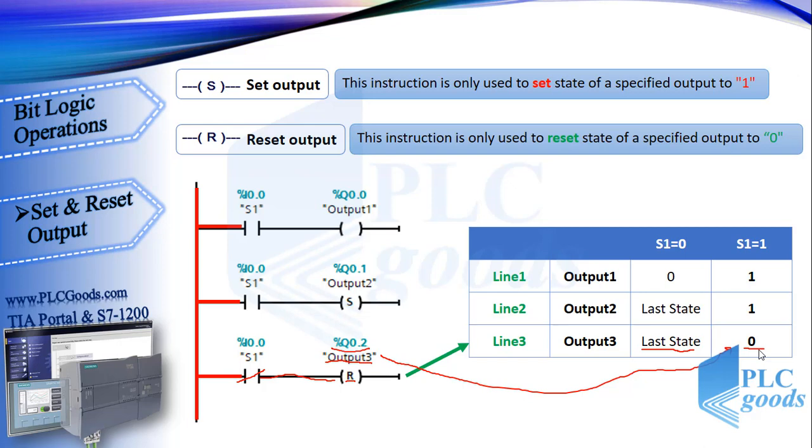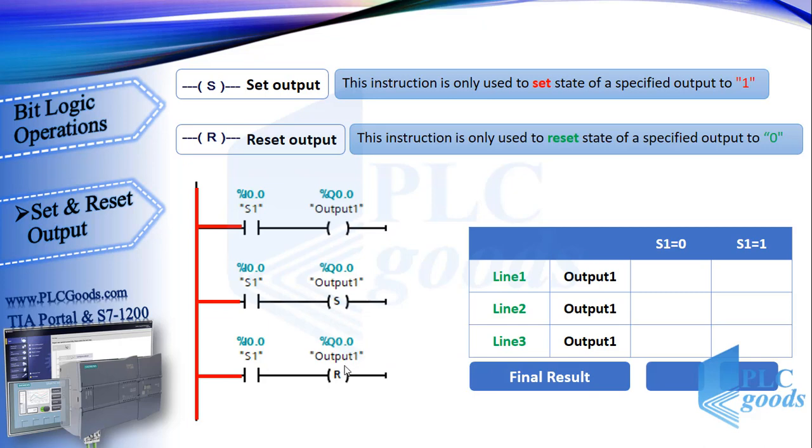But now pay attention here. In these three lines, three different addresses have been used for three outputs. Now what's your opinion of this program, which has used the same address for all outputs? The main point is how CPU executes its program. CPU runs its program from first line to last, then updates all outputs, after that reads and stores state of all inputs, and again, based on stored inputs and outputs, runs its program. So CPU doesn't use physical input or output in middle of executing its program.